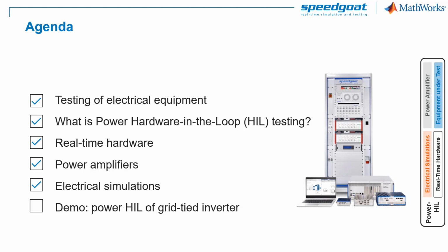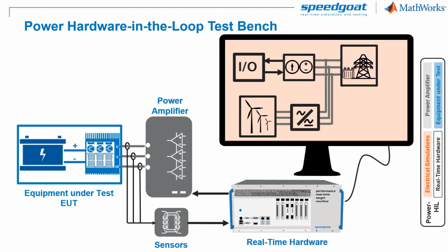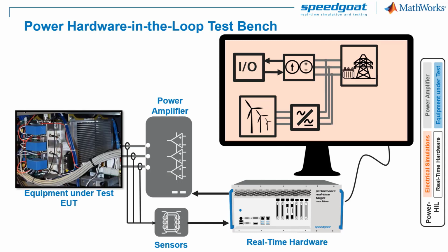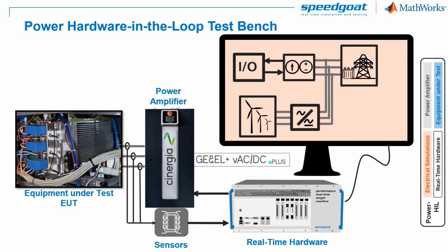Now let us move to the Power Hardware-in-the-Loop demo. We'll be using Power Hardware-in-the-Loop testing to commission a grid-tied inverter rated at 15 kVA with a two-level three-phase inverter topology, including an LCL output filter. It is connected to a 60 kVA power amplifier from Cinergia, specifically a GE and EL plus, capable of sinking and sourcing both alternating and direct currents. It can also act as a voltage source or as a current source, where G stands for grid emulator and EL stands for electric load. Therefore, it operates as a four-quadrant power amplifier.